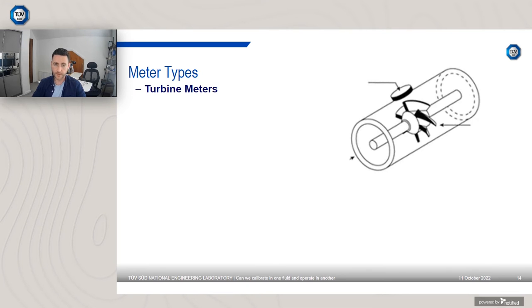Now, you get liquid turbine meters, but you also get gas turbine meters, and ultimately a liquid turbine meter should only be used in liquid flow, and a gas turbine meter should only be used in gas flow. So straight away, you cannot calibrate a gas turbine meter in water and use it successfully. Common knowledge, but I just wanted to drive that point home. It's not applicable for all meter types.